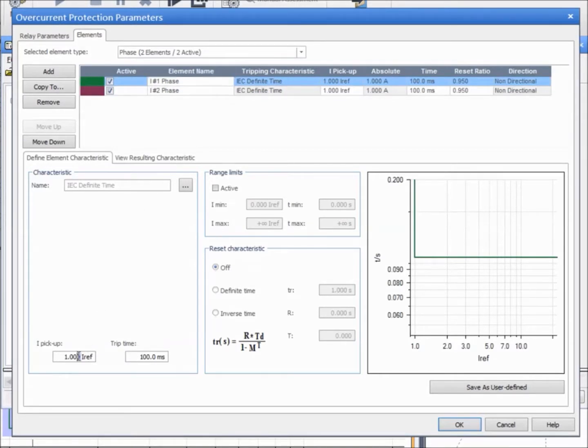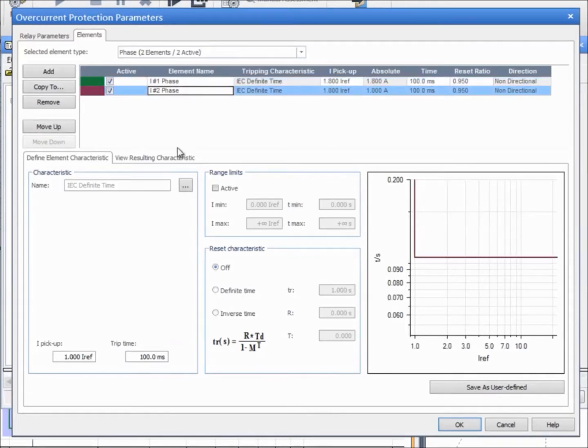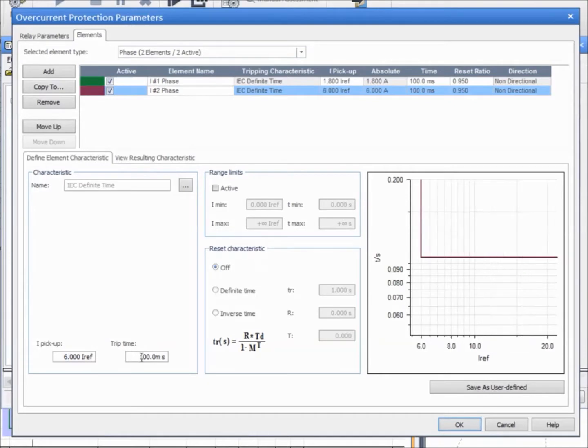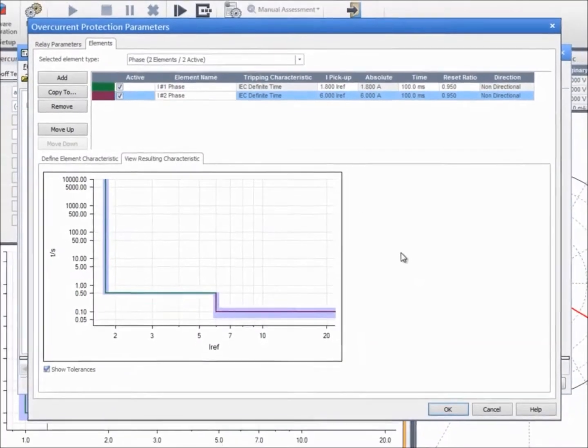The first element trips at 1.8 amps with a time delay of 500 milliseconds. The second element trips at 6 amps with a time delay of 100 milliseconds. No range limits or reset characteristics are specified. Finally, we check if the data we have entered matches the resulting characteristic.